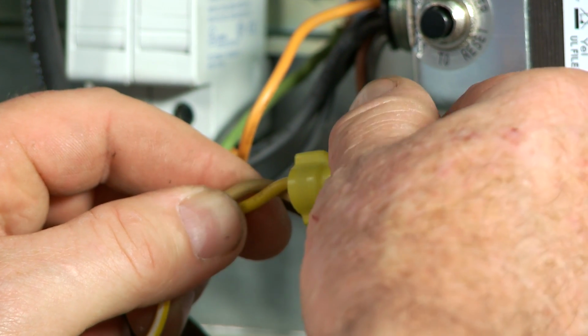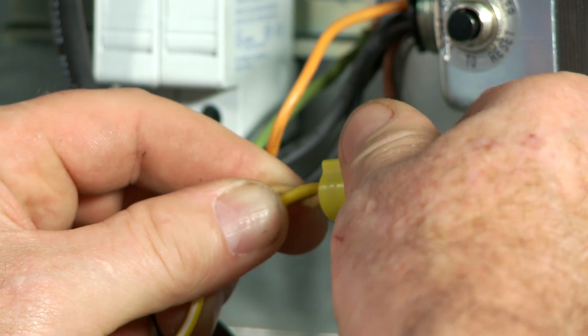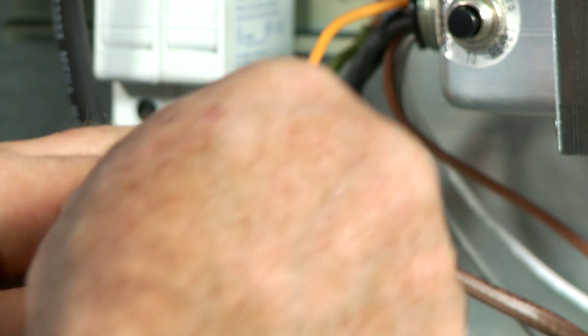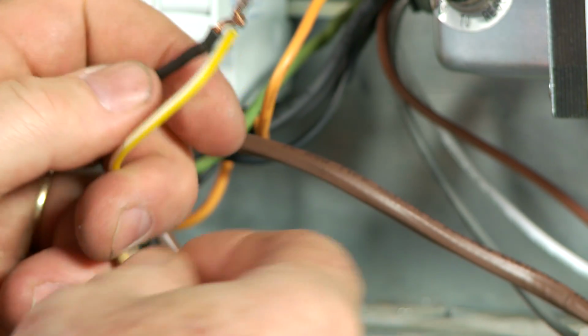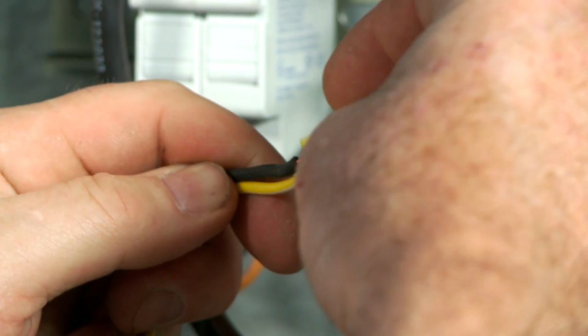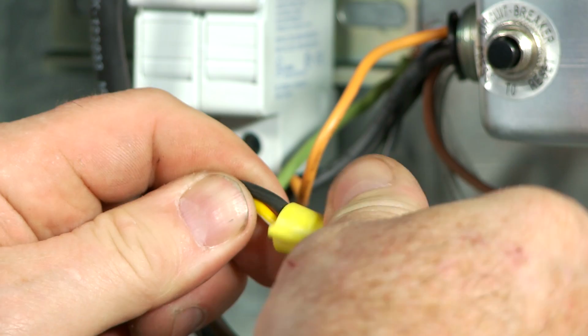To complete the power connection to the controller, take the black and white 16-3 cables and wire nut the bare leads to the yellow and yellow-white secondary wires from the transformer. Wire nut the yellow transformer wire to the white wire of the 16-3 bundle, and wire nut the yellow-white transformer wire to the black wire of the 16-3 bundle.